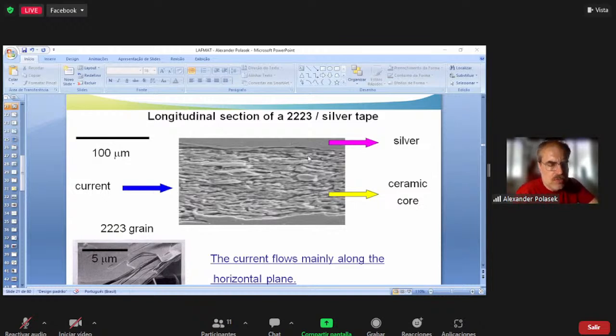However, this is an interesting question, because possibly you don't need very long cables to make superconducting cables useful. Short cables may be helpful too. Why? Because in the electric grid you often have bottlenecks, places where you don't have space, mainly in urban areas or where there are environmental problems, so there's limited right of way. The right of way is the space available to install an overhead line. If you cannot install an overhead line, you need to use underground cables, and underground cables, even conventional ones, are more expensive than overhead lines.